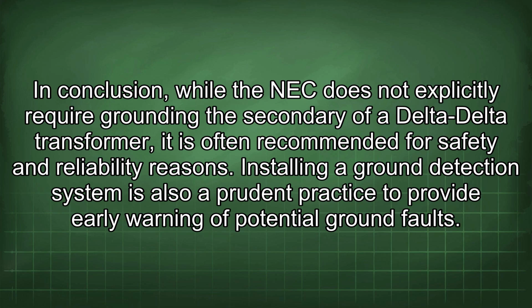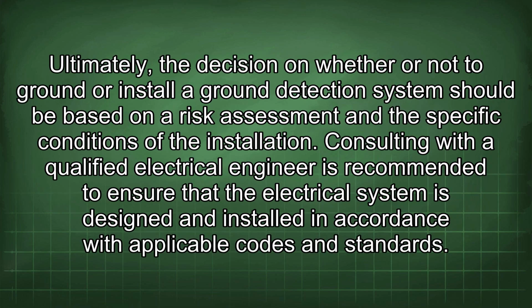In conclusion, while the NEC does not explicitly require grounding the secondary of a delta-delta transformer, it is often recommended for safety and reliability reasons. Installing a ground detection system is also a prudent practice to provide early warning of potential ground faults. Ultimately, the decision on whether or not to ground or install a ground detection system should be based on a risk assessment and the specific conditions of the installation. Consulting with a qualified electrical engineer is recommended to ensure that the electrical system is designed and installed in accordance with applicable codes and standards.